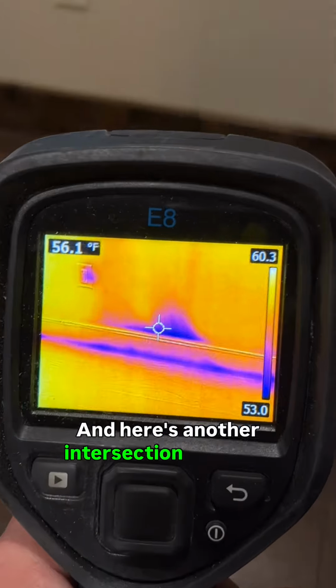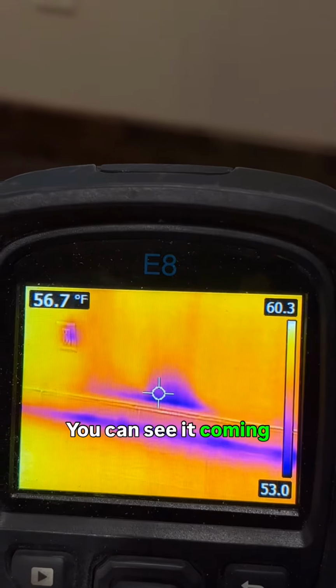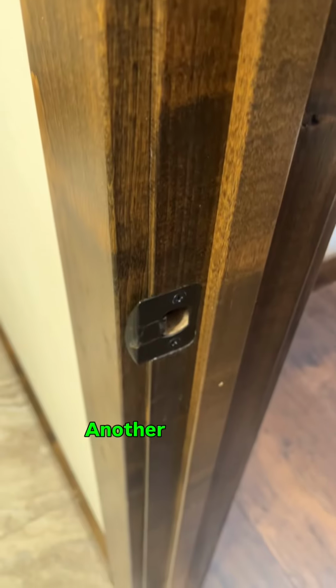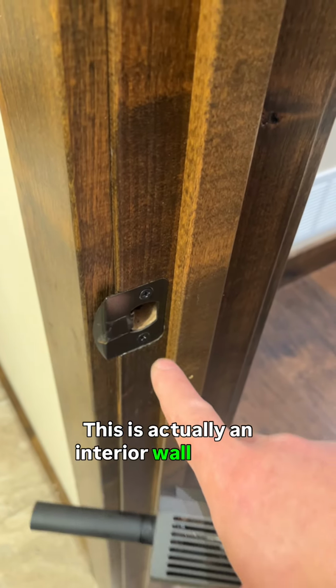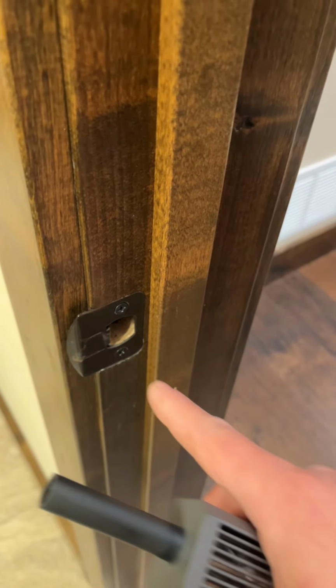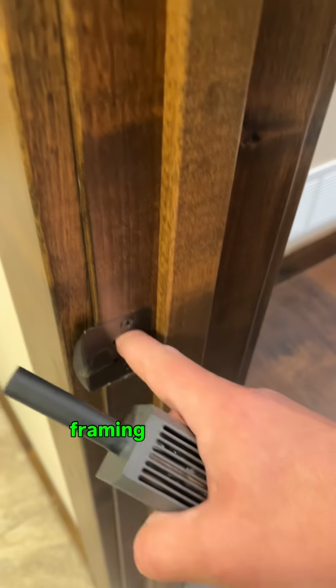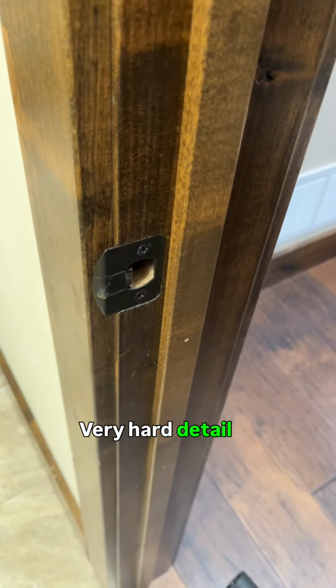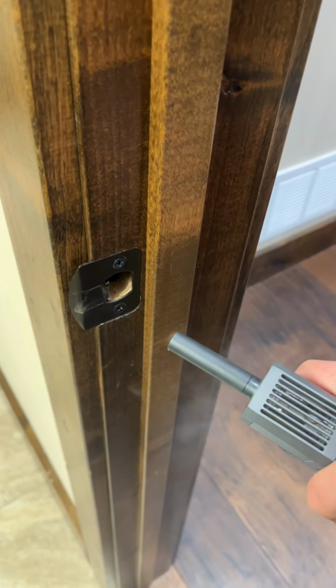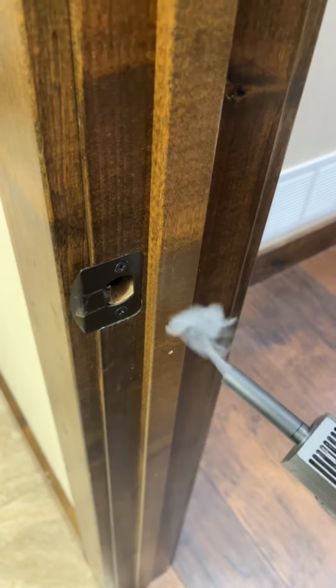And here's another intersection between a floor and a wall. You can see it coming up right there behind the trim. And same story there. Another common spot, this is actually an interior wall, but we have a strike plate for a door. And then behind there is framing, and that framing goes up into the attic. And there's little gaps and cracks and whatever else that didn't get sealed. Very hard detail to get right. We do have a fair bit of air leakage there.